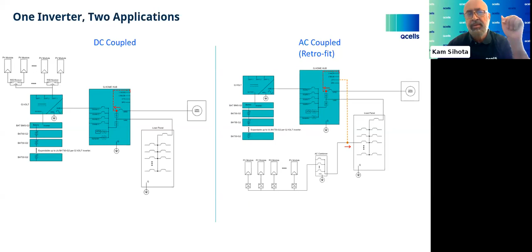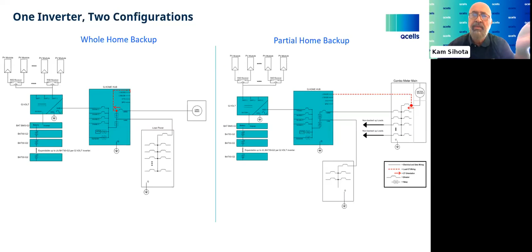Depending on whether you're doing a partial or whole home backup, it's the same components and approach, but it has to do with where you tie in your backup panel or main panel. On a larger system, you may need multiple battery cabinets - this diagram shows one, but on the left-hand side you can see inputs 2, 3, and 4 that aren't connected in the hub there. So up to 4 systems, taking it all the way to 80 kilowatt hours, and 4 times 7.6, which is about 30 kilowatts of power.